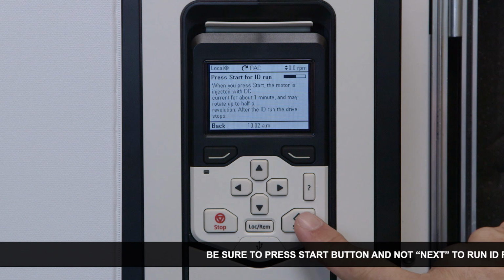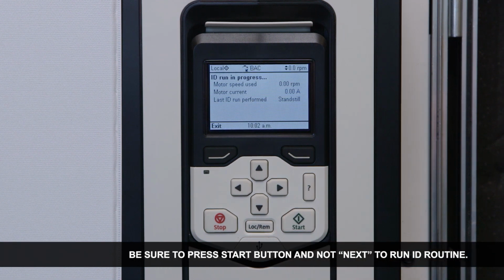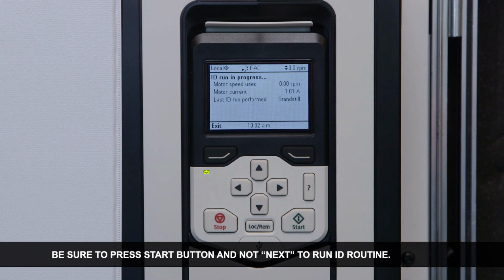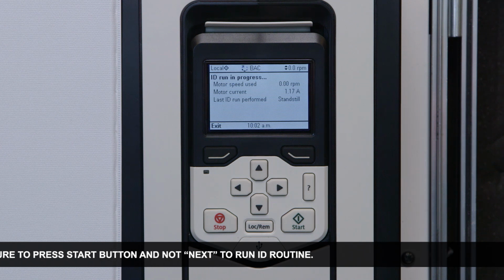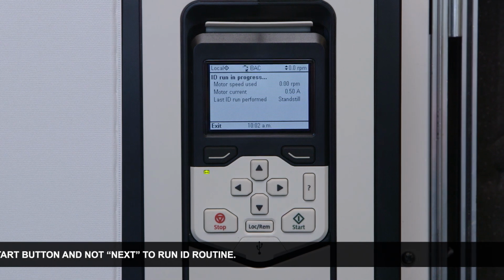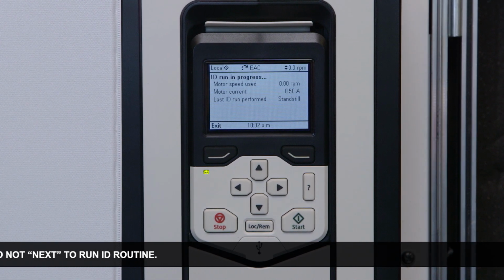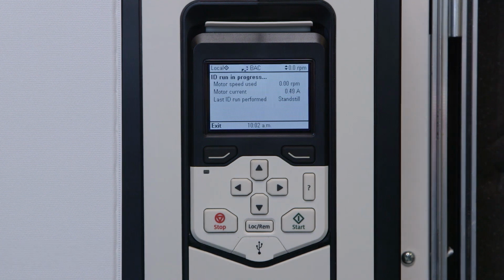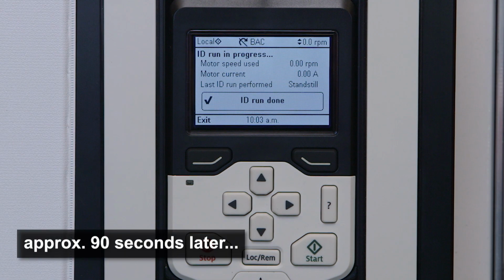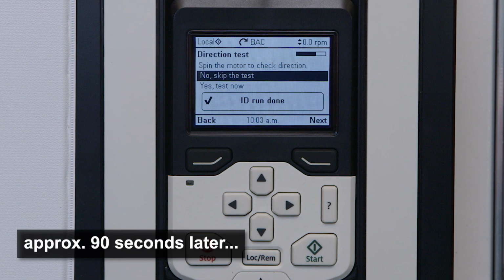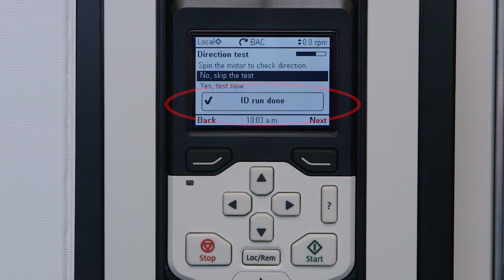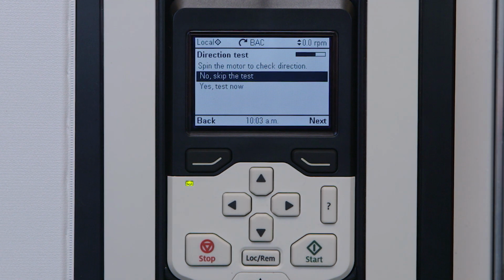Once the ID run mode is set, we need to run the ID routine. Press the green Start button on the keypad. Wait for the VFD to complete the ID run. This can take a couple of minutes, and the fan shaft may rotate up to half of a revolution. When the ID run is complete, the display will briefly exhibit the message ID run done. When you see this message, the VFD will automatically proceed to the direction test.